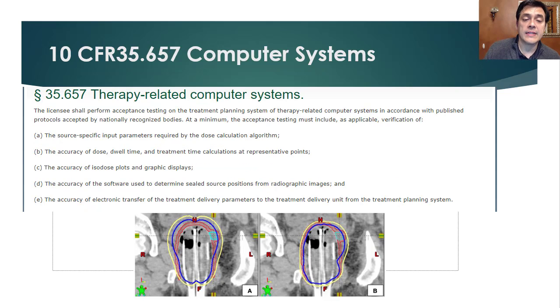CFR 35.657 Computer Systems. For the treatment planning system, for the therapy-related computer systems, there needs to be some checks performed, and there needs to be acceptance testing on the treatment planning system to demonstrate that the published values and published protocols generate consistent results for simple test plans before we go and try and create patient-specific test plans. So the source-specific input parameters required by the dose calculation algorithm need to be verified. The accuracy of dose, dwell, and treatment time calculations at representative points need to be checked.